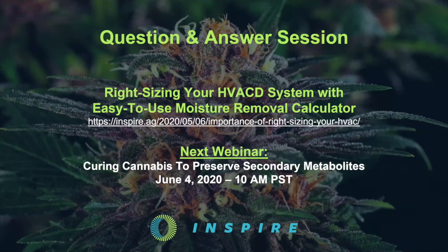Yeah, absolutely. I'll take this one. I mentioned the technologies before for dehumidification and how to make a less energy intensive growing operation. There's a number of dehumidification technologies. We call them in our products a coil runaround loop. There's an air-to-air heat exchanger around the same cooling coil mechanism that we talked about before. There are liquid and dry desiccant systems that can be used.